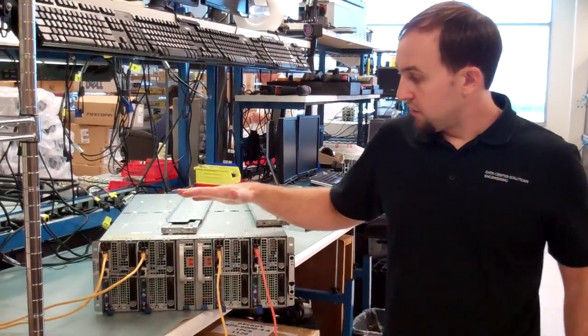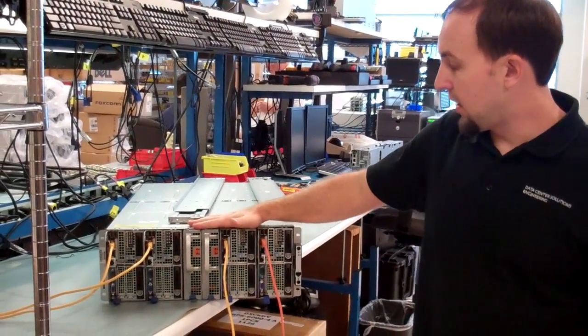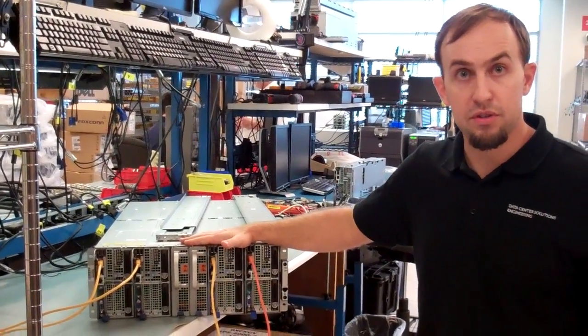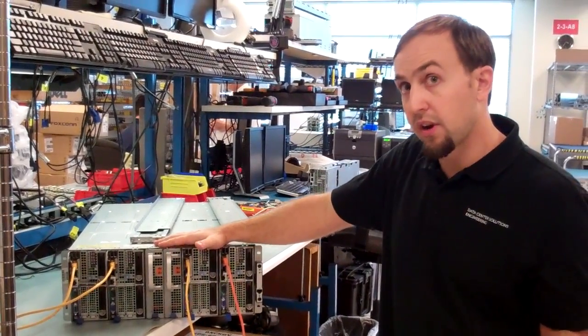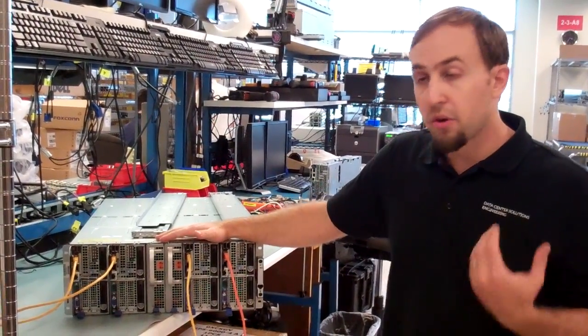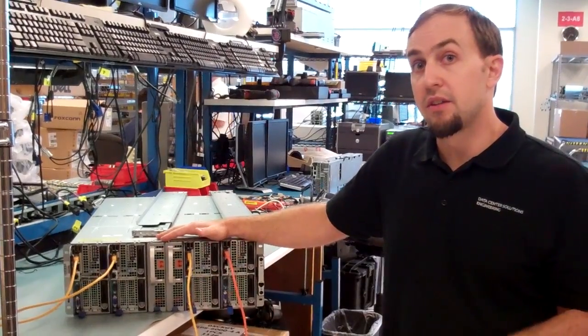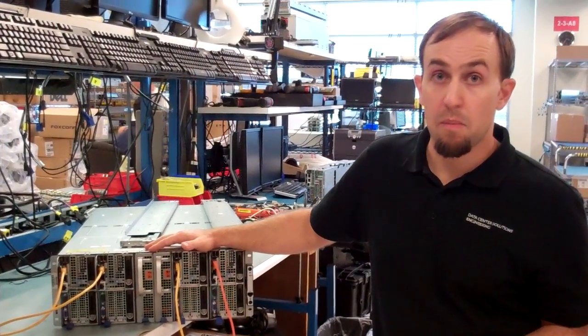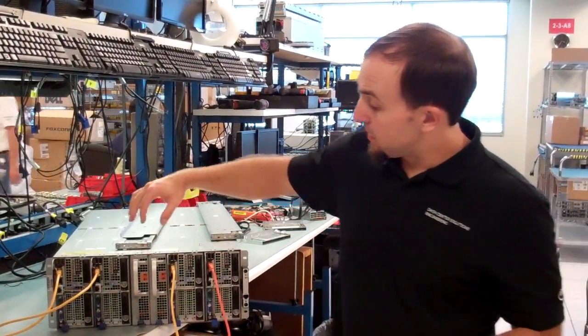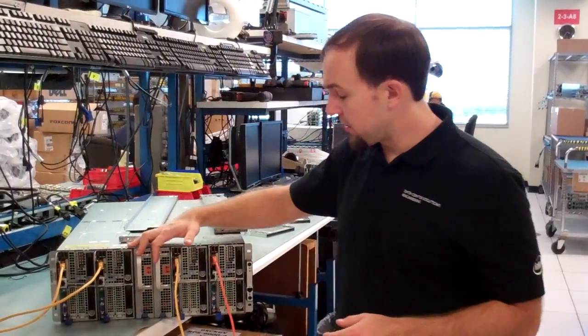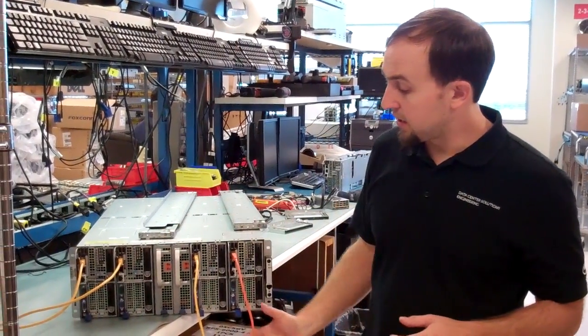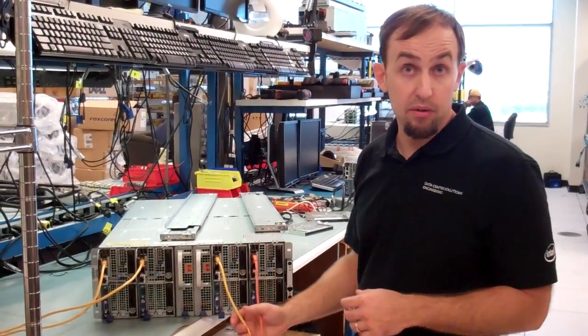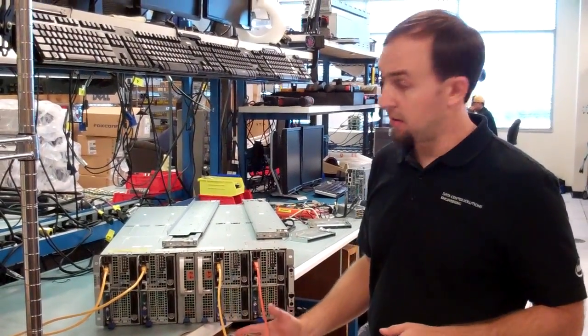Since this is a front cabled system versus the traditional rear cabled system, one of the questions that we get a lot is how to do cable management for this. Since the power supplies are in the middle, what we generally recommend is that you end up building multiple cable bundles in front of the rack.